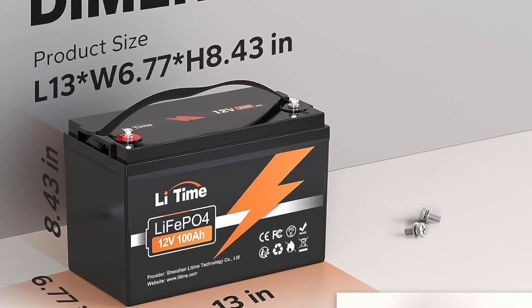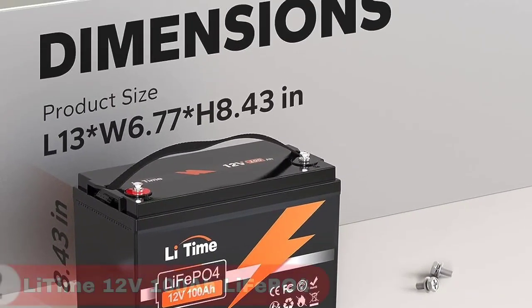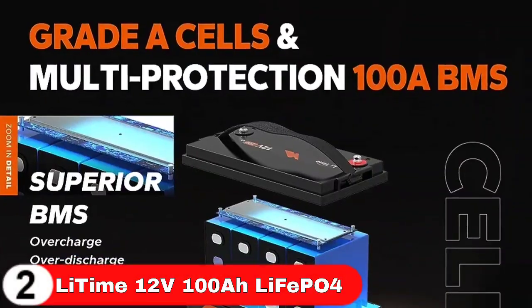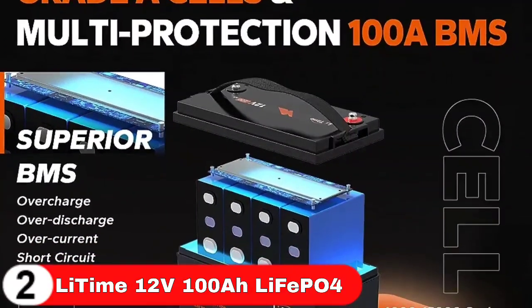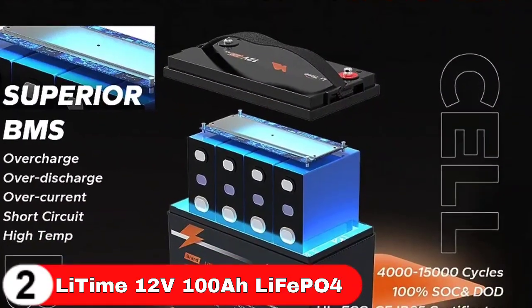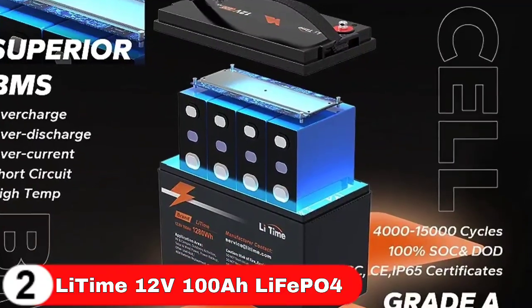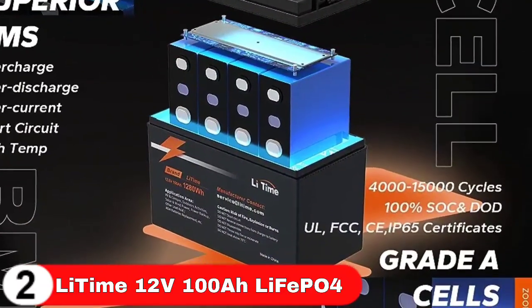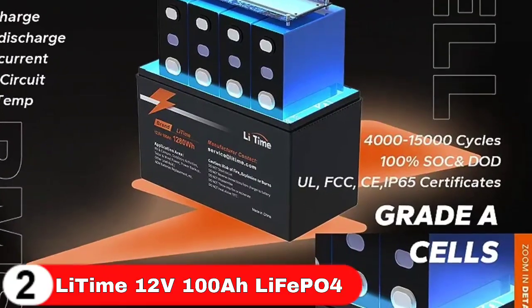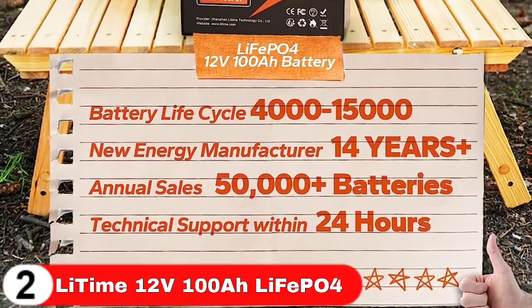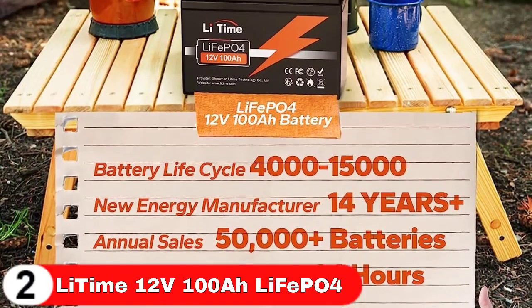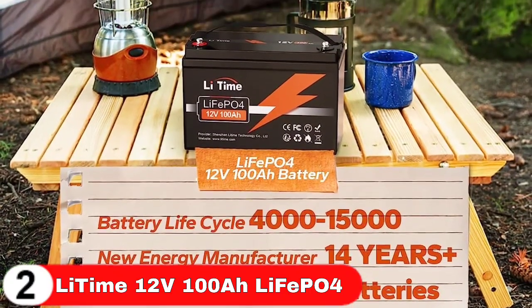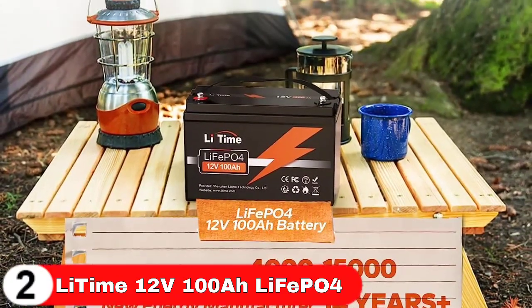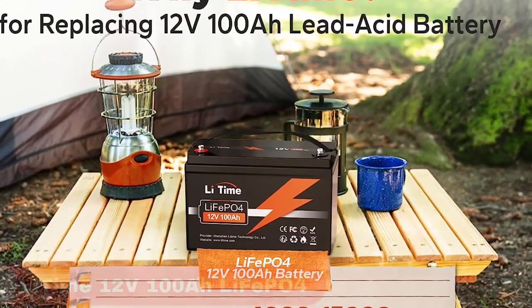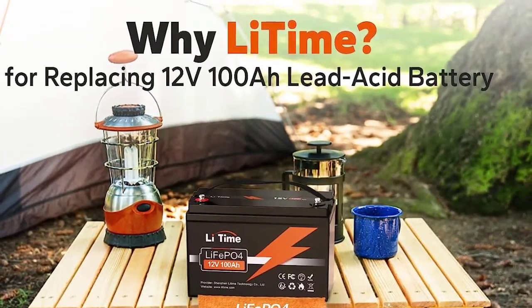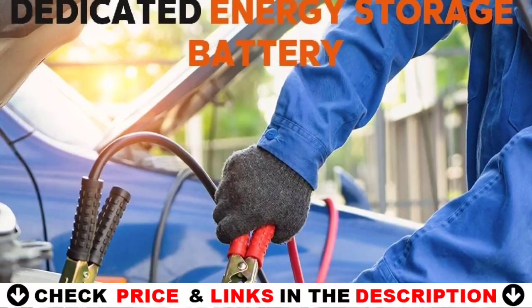LiTime uses lithium iron phosphate, Li-FePO4, cells, which have a reputation for being both durable and safe. The battery is rated at 100Ah, which is 1280 watt-hours at 12.8 volts. 100A is also the max continuous charge/discharge current, meaning it can output up to 1280 watts. As I'll show in my test results, it can put out more than this, but 100Ah is what it's rated at. The battery has an IP65 rating, meaning it has enough protection to handle dust and low-pressure water jets like light rain.